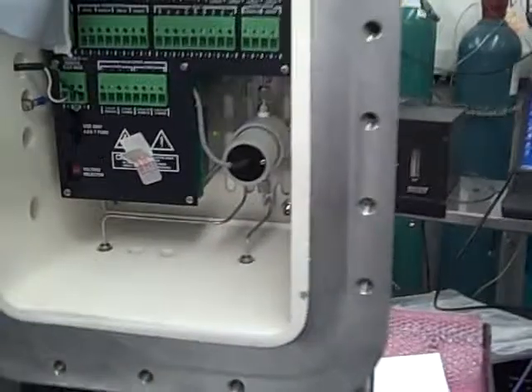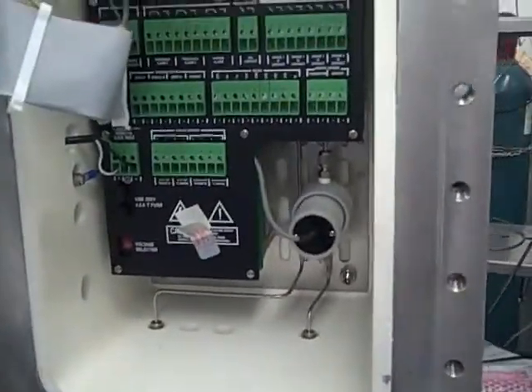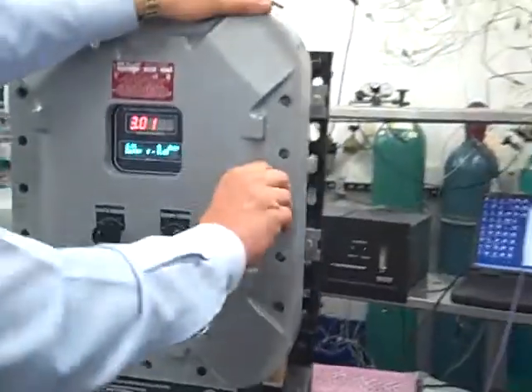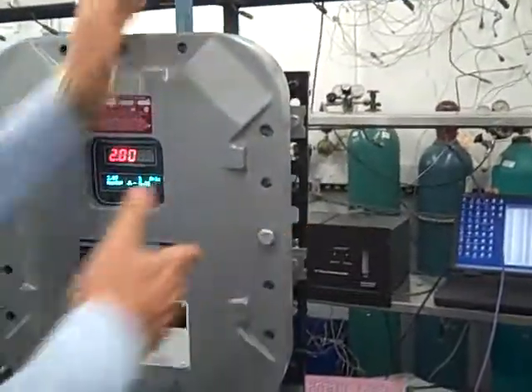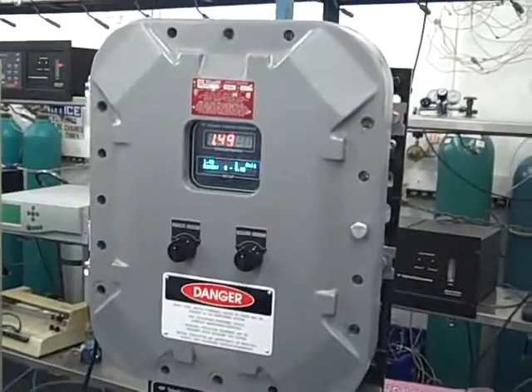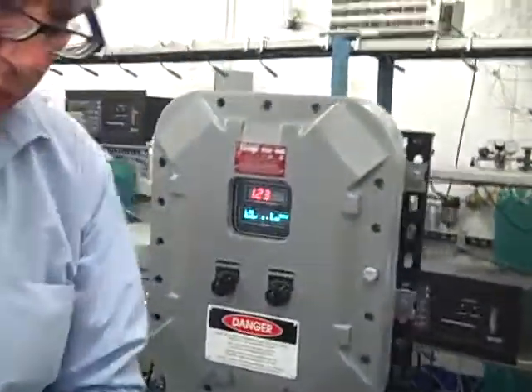It's that simple. Now you'll have to replace that sensor occasionally. So the first step after sensor installation is calibration, generally speaking. For a trace sensor, the sensor needs to be installed and purged with nitrogen or process gas. We would recommend typically 24 hours, unless you're using the InstaTrace option, which allows the sensor to come down very quickly, typically within an hour. You can calibrate after about an hour with the InstaTrace. If you don't have the InstaTrace option, purge that sensor for about a day to bring it down low, and then we recommend calibrating typically on 80 ppm or 8 ppm gas, if it's a trace analyzer.